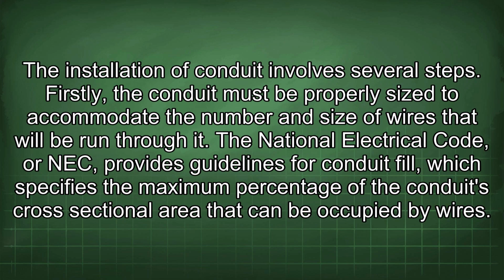The installation of conduit involves several steps. Firstly, the conduit must be properly sized to accommodate the number and size of wires that will be run through it. The National Electrical Code, or NEC, provides guidelines for conduit fill, which specifies the maximum percentage of the conduit's cross-sectional area that can be occupied by wires.